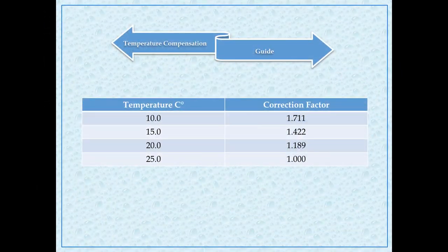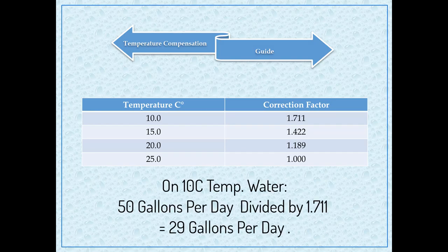On the next slide, we're showing you a correction factor of what temperature does to that membrane. The easiest way to understand this is you might have heard that that membrane might be rated at 50 gallons per day, but no one ever bothers to tell you that that's if the water was sitting at 25 degrees C. So 25 degrees C is going to be about 75 degrees Fahrenheit. So this correction factor is showing you that the unit would actually make that kind of volume if the temperature was there. But you'll see that if the temperature was 10 degrees C, or in parts of the Canadian marketplace where the water would be 5 degrees C, it would create an even further correction factor that you would be looking at. You take that correction factor and you would divide that by what the membrane is rated to do. So in these situations, you can clearly see that a 50 gallon per day membrane may only make 25 gallons in a particular application if the water is very cold.